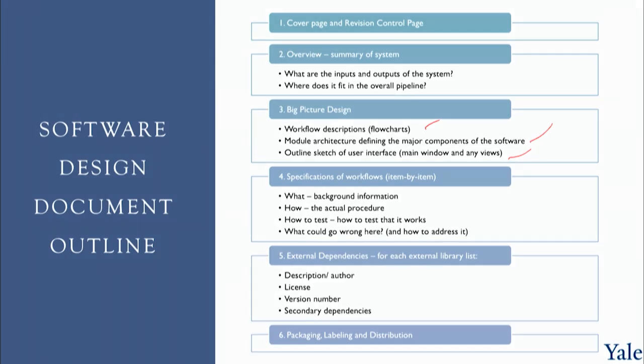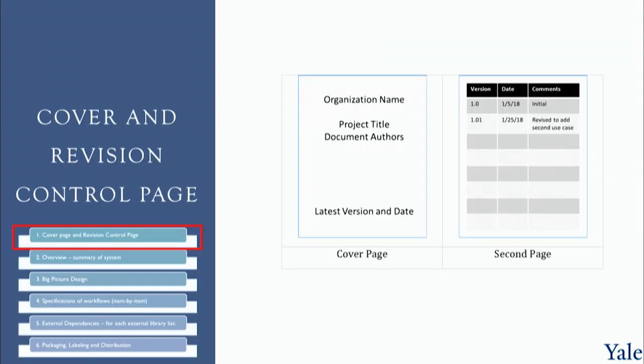That's more domain specific. Okay, the cover and revision control page look identical to what we have for the system requirement specification. Again, this is the control page, which lists the changes done in this document so we can see how it was changed and when. And the title page includes a signature and a date here, 1/1/2019, and somebody signs it. This is for the design history file, so we have the evidence that we've had a plan and that we followed that plan, and this is part of that process. This is the design controls guidance. So let's start at the beginning.